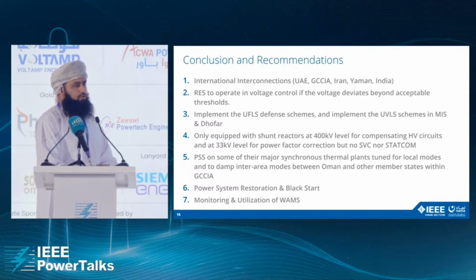We also need to introduce some operational measures, such as under frequency load shedding and under voltage load shedding, to maintain system stability. And also tuning the existing power system stabilizer in order to maintain the system security. And we need to get benefit from the wide area monitoring system, so we need to address all the phenomena and events that happen due to having a high rate of renewable energy in the background. That's all. Thank you so much for listening.